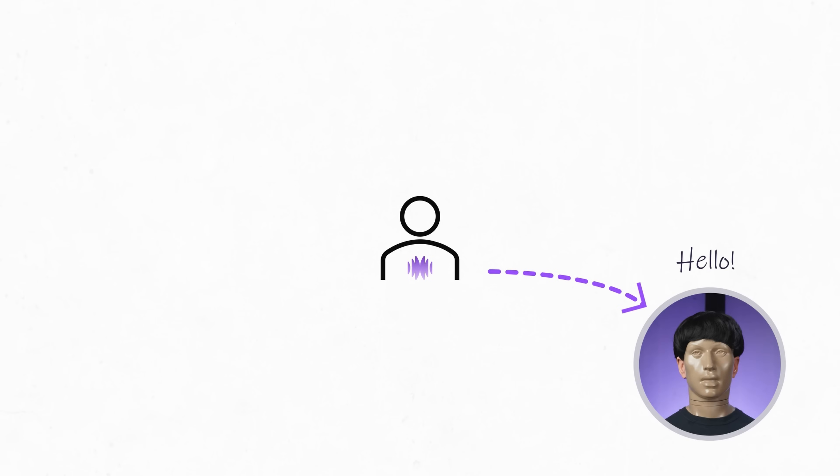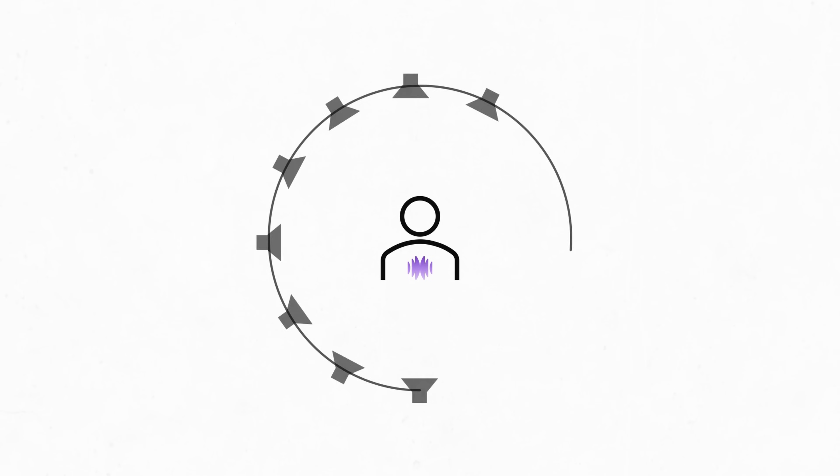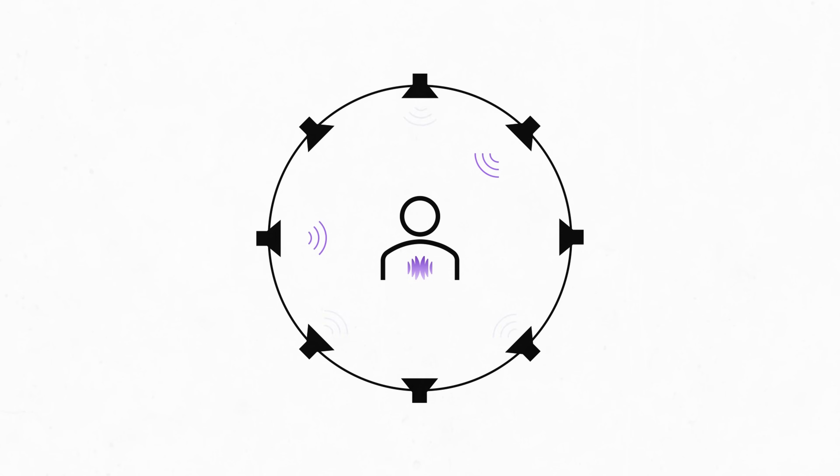At HearAdvisor, we have an industry-standard acoustic mannequin called KEMAR, and we use an immersive 3D audio presentation method known as ambisonics to make recordings of real-world environments in our acoustic lab. Those recordings are analyzed based on a common age-related hearing loss, and we look at each hearing aid's speech and noise performance, feedback control, own-voice sound quality, and streamed music audio quality.